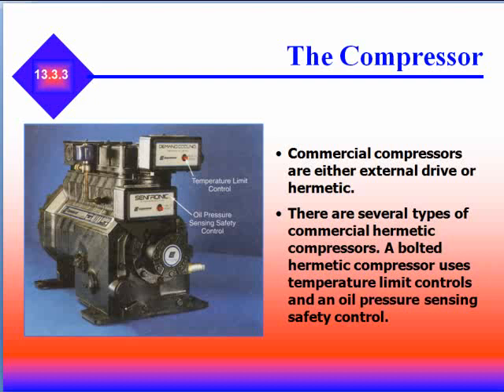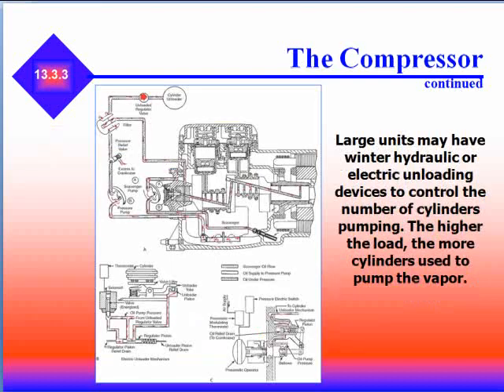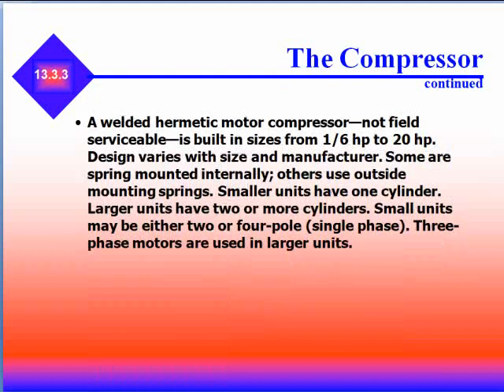Commercial compressors are either external drive or hermetic. There are several types of commercial hermetic compressors. A bolted hermetic compressor uses temperature limits and oil pressure sensing safety devices; large units may have hydraulic or electric unloading devices to control the number of cylinders pumping — the higher the load, the more cylinders are used to pump vapor. A welded hermetic compressor, not field serviceable, is built in sizes from 1/6 to 20 horsepower, and design varies with size and manufacturer.